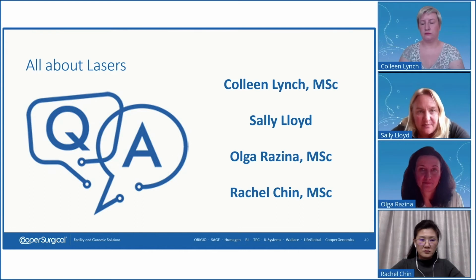I would say it's more a case of an expectation of how your laser should be performing. So when I talked earlier about the hole size calibration, we're expecting to see a hole, for example, of this size. And then we come to our laser one day and the hole's really small. Something's changed. So you go through that checklist of things I talked about. But if you've still got that problem, then something has happened to the laser.